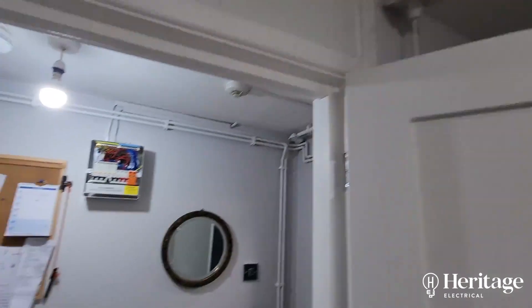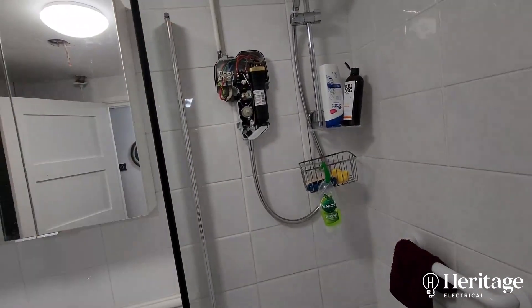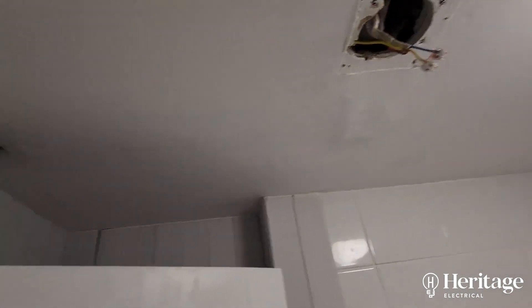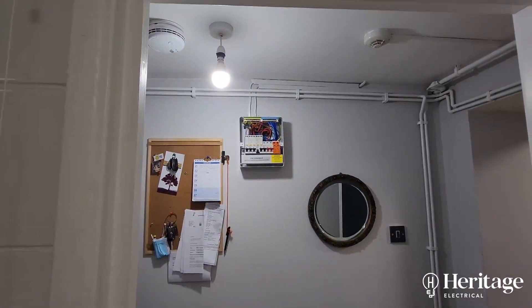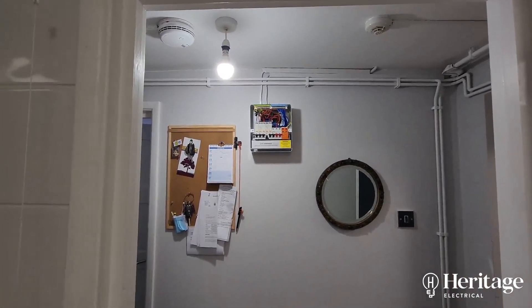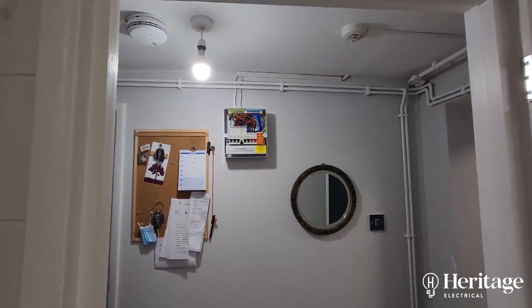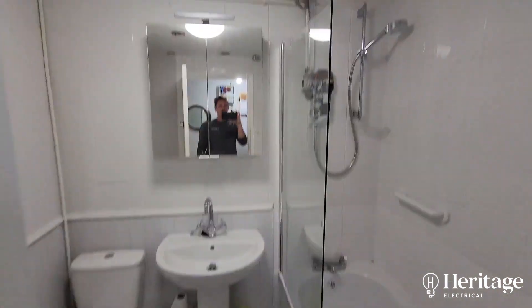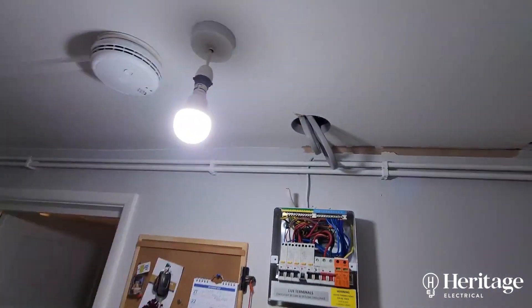What we're going to do is completely rewire the circuit in 10mm cable - this is pulling 40 amps plus - so new pull switch, new 10mm cable from the consumer unit to the pull switch and then to the shower, to get rid of any dodgy joints. We're going to change the consumer unit for a Hager RCBO board, and I'm going to do an installation certificate and test the whole flat so he's got certificates for his insurance.